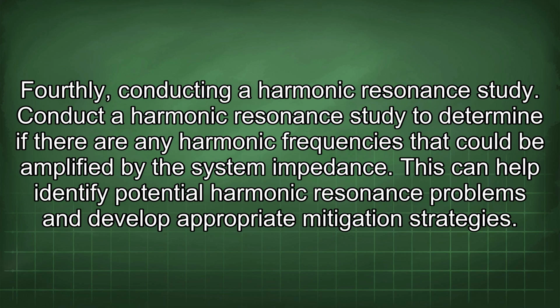Fourthly, conducting a harmonic resonance study. Conduct a harmonic resonance study to determine if there are any harmonic frequencies that could be amplified by the system impedance. This can help identify potential harmonic resonance problems and develop appropriate mitigation strategies.